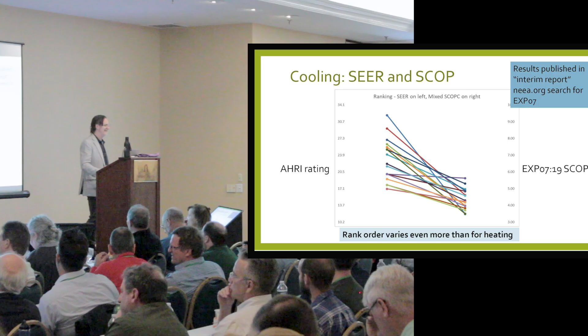I'm like, underreported, yeah, but this is going the other way. But it was a legitimate point. We didn't test these units using the AHRI test. We tested them and then compared them to the AHRI rating. On the cooling side, the SEER ratings were all over the place. There were none that matched, or only maybe one pair that matched. But you can see the rank order is really different, right? Also, the overall difference is bigger, suggesting that maybe SEER is even more overly optimistic than HSPF. But again, we don't know. Is our test method actually better? We don't know.